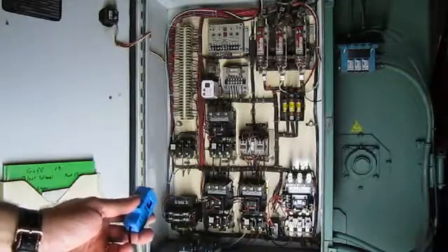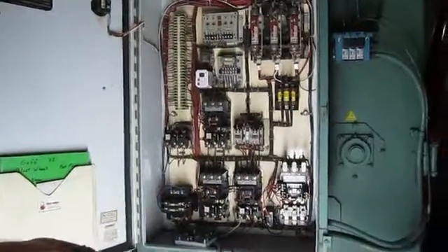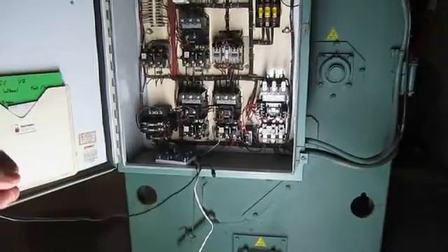However, what we can do is right down here is the main motor starter for the spindle up on top. That's a shot blasting machine. It actually throws the shot. So if that spindle is running, there's a pretty good chance that you're producing parts out of this machine. If the spindle is not running, you are most certainly not producing parts at all. So that's where I would choose to put the current transformer, is right down here on one of the legs of that spindle motor.